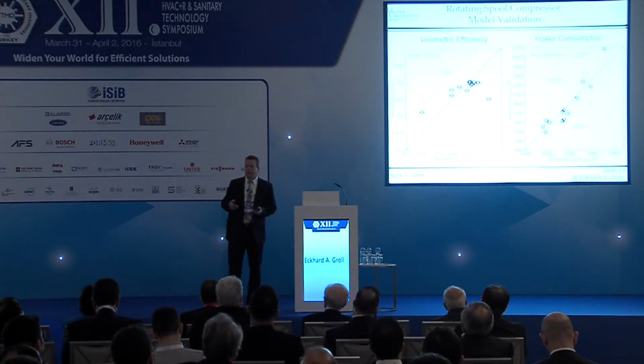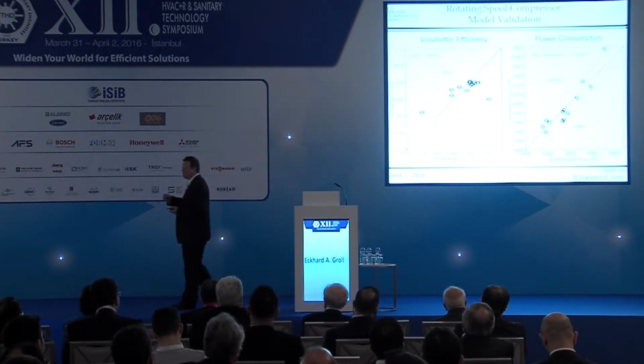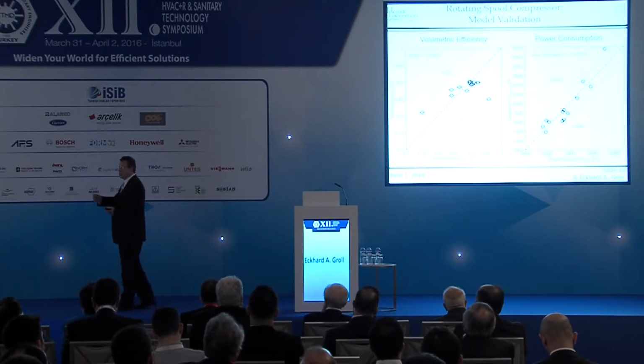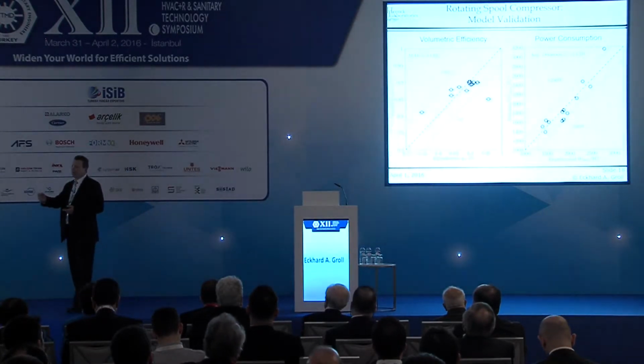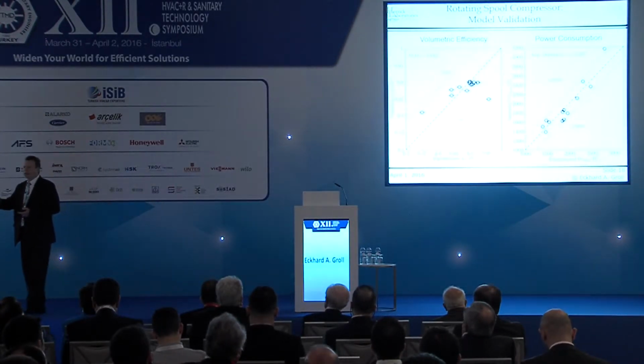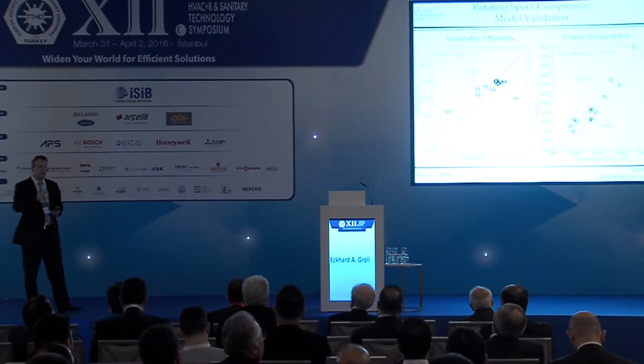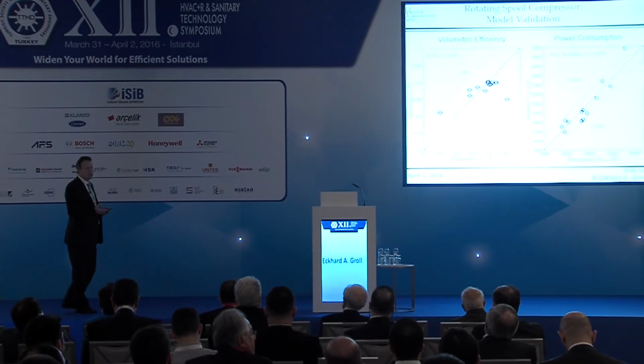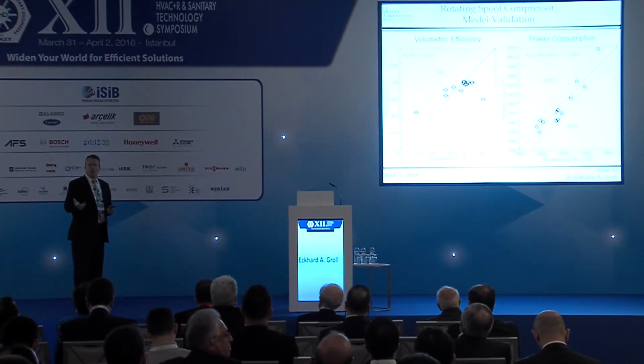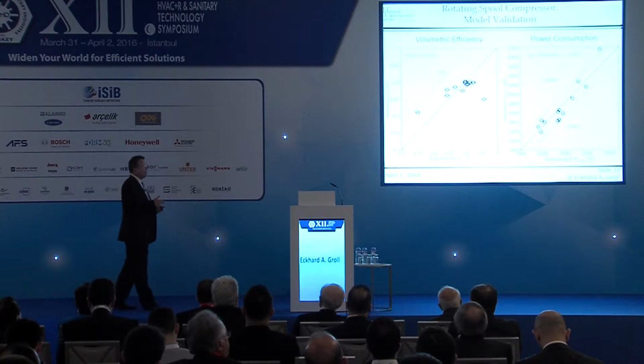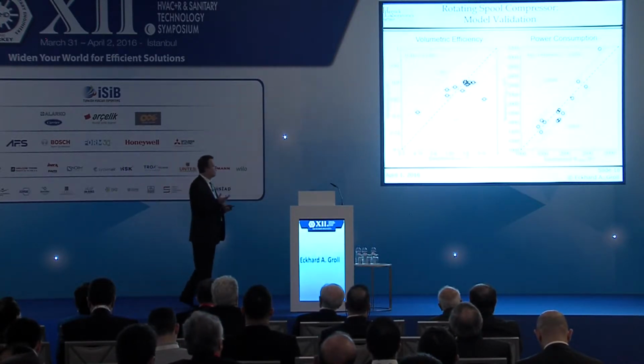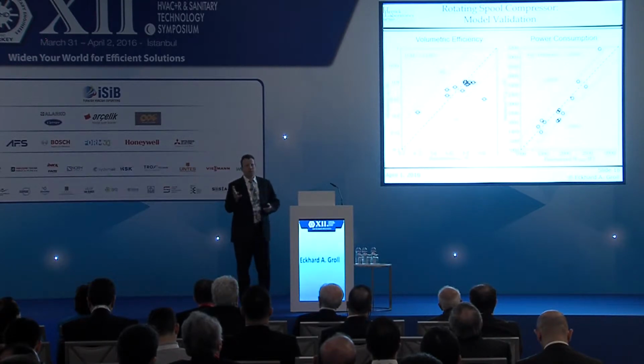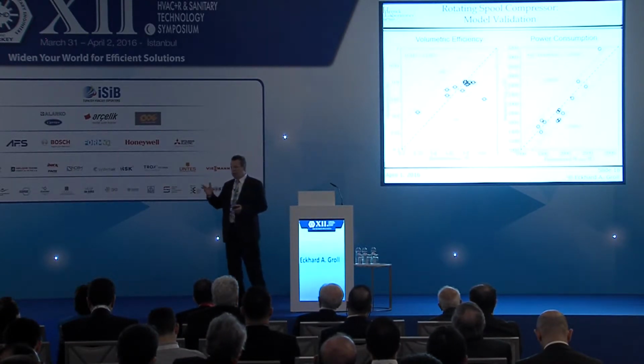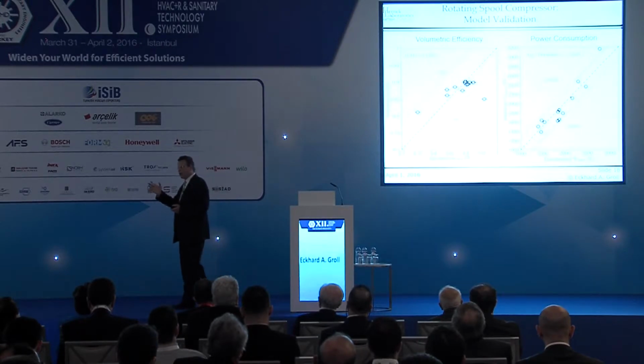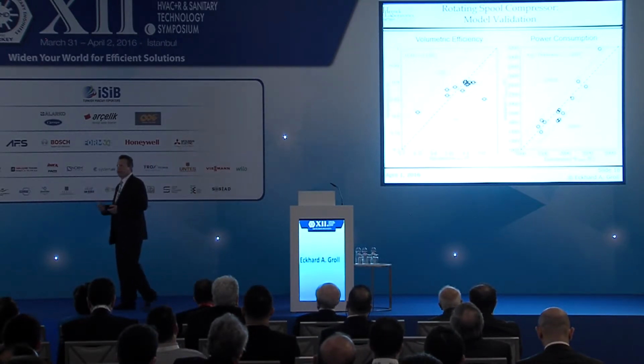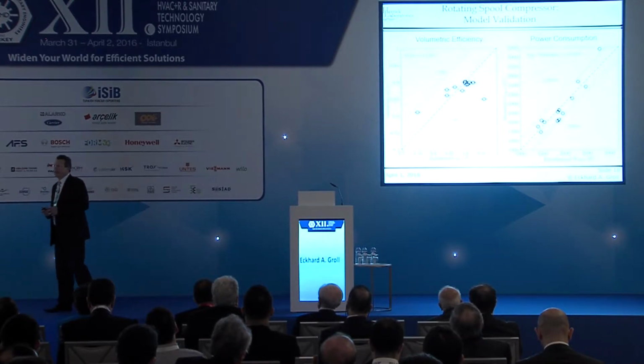And we typically validate our models. Validate means you have to have a prototype compressor. You have to conduct experiments. You have to see how accurate your model is against good, solid, accurate experiments. So we put compressors on calorimeters, on test stands to measure mass flow rate and power consumption. Mass flow rate is typically indicated by volumetric efficiency. Power consumption is quite often indicated by an overall isentropic efficiency. There are other efficiencies that you can use, or you can compare power consumption directly, as done in this case.